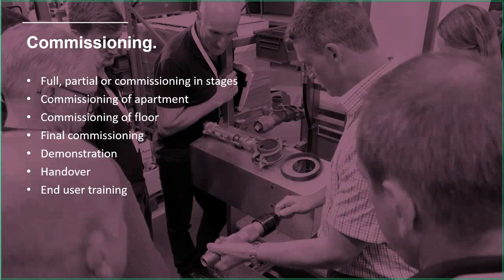And as I said, there's a lot of coordination required between the various services, which we'll come on to a bit later. So you've got commissioning as you go. It may well be that the sprinkler contractor is going to do some tests and checks independently, i.e. not official ones, not witnessed ones, but will probably want to do some commissioning as he goes to make sure that things are in order. And then you would have final commissioning at the end, which is basically the important bit, the one that is going to be witnessed. It's going to be witnessed by relevant people.